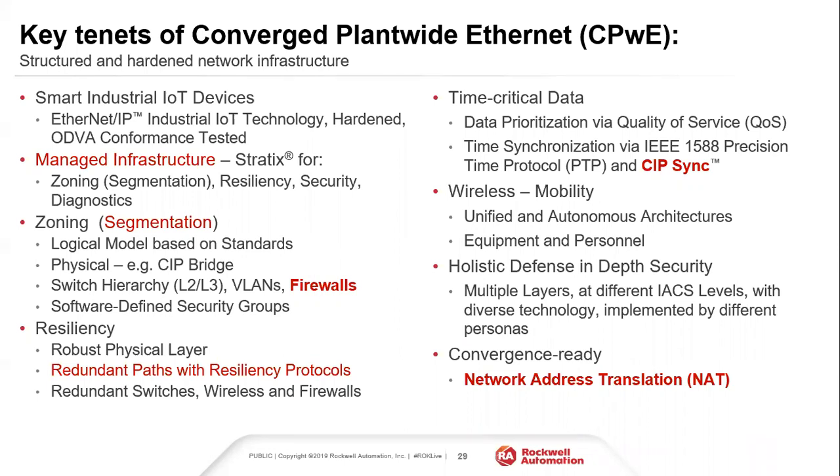So what we do, for motion-based applications or precision-based applications, is we have what's called time synchronization, and it makes it so that every single one of the controllers has the same time and date stamp, and it also has propagation delays so that when I send a command through a controller to a peer-to-peer network, it accounts for any delay that goes through. On the low-hanging fruit side of it, what you can do is make it so that your managed switch network, your controllers, and all of the server equipment are all on the same timestamp. So that when you record data on Historian or when you see alarm and event information, they're all on the same timestamp.